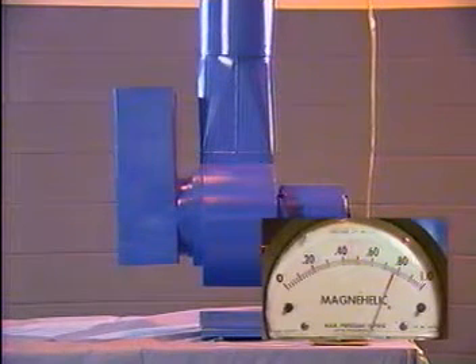That translates into energy and financial savings. But poorly designed inlet boxes are not the only way a system can go bad. Fans work by changing the direction and velocity of the incoming air. If air is spinning in the same direction as the wheel, volume and pressure are reduced. If air is spinning in the opposite direction of the wheel, brake horsepower and noise increase. Fans work best when air flows straight into the inlet.